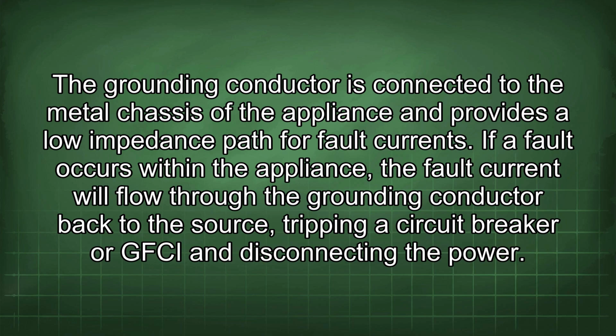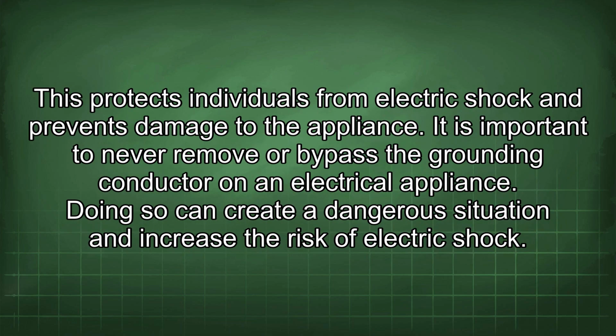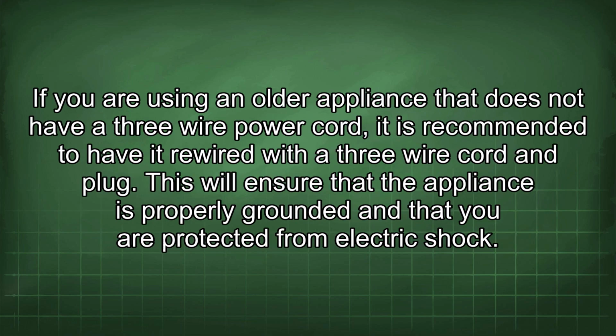If a fault occurs within the appliance, the fault current will flow through the grounding conductor back to the source, tripping a circuit breaker or GFCI and disconnecting the power. This protects individuals from electric shock and prevents damage to the appliance. It is important to never remove or bypass the grounding conductor on an electrical appliance. Doing so can create a dangerous situation and increase the risk of electric shock. If you are using an older appliance that does not have a 3-wire power cord, it is recommended to have it rewired with a 3-wire cord and plug. This will ensure that the appliance is properly grounded and that you are protected from electric shock.